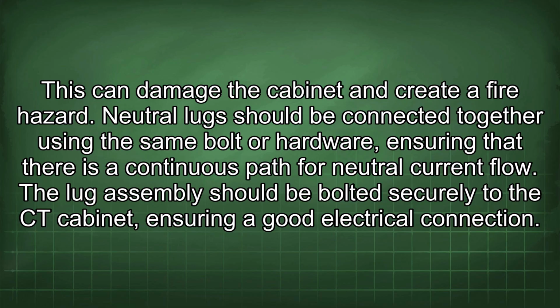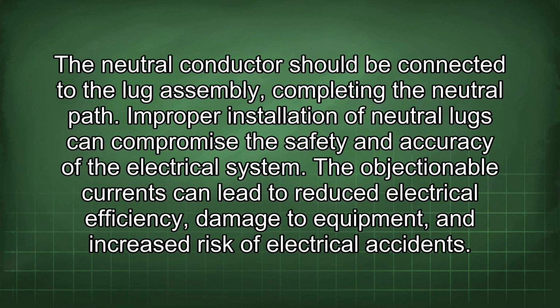Neutral lugs should be connected together using the same bolt or hardware, ensuring that there is a continuous path for neutral current flow. The lug assembly should be bolted securely to the CT cabinet, ensuring a good electrical connection. The neutral conductor should be connected to the lug assembly, completing the neutral path. Improper installation of neutral lugs can compromise the safety and accuracy of the electrical system.